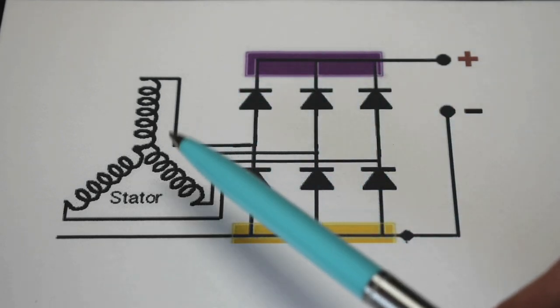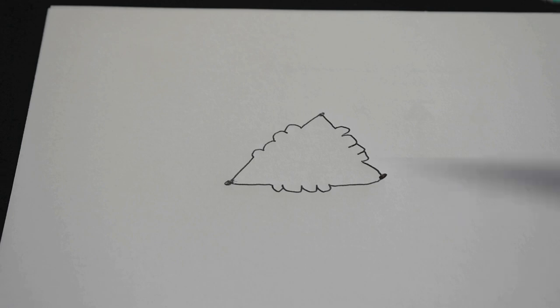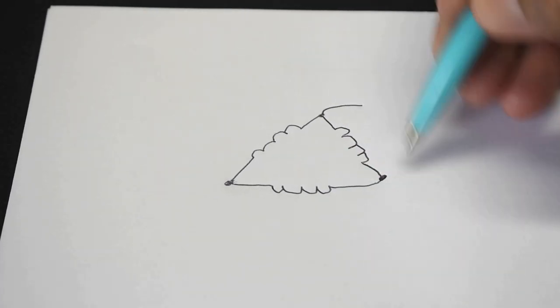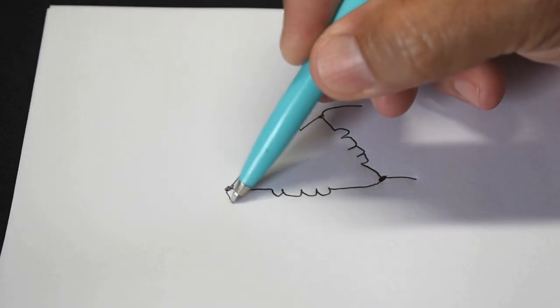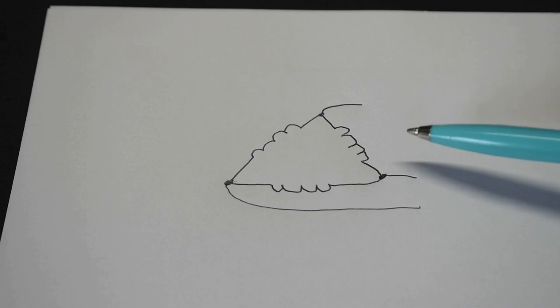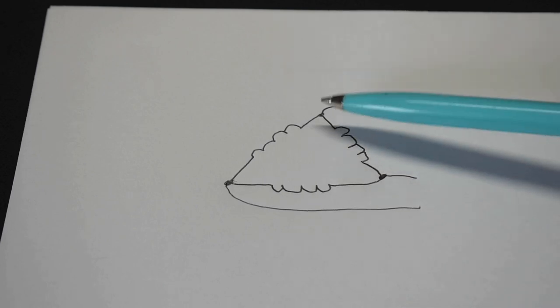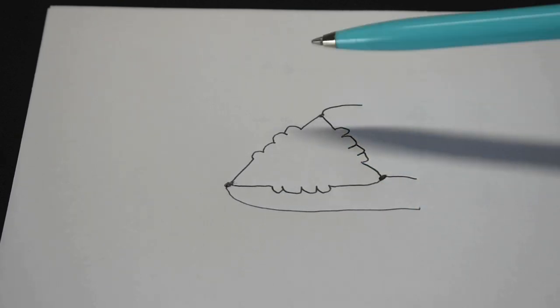Just to show you if it's not a star configuration, a delta configuration looks like what you see right here. Instead of having all three windings connected at one point. Here you have one winding, two winding, three windings. And then you would have your outputs like this. That would be delta. There are differences between the two configurations. And normally or typically you would find the delta configuration in generators.